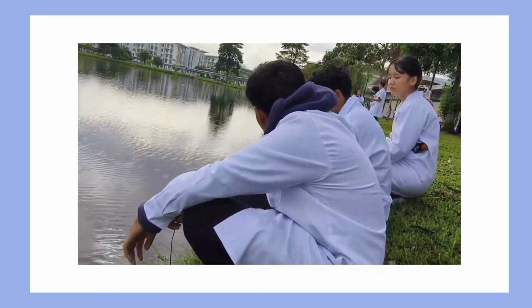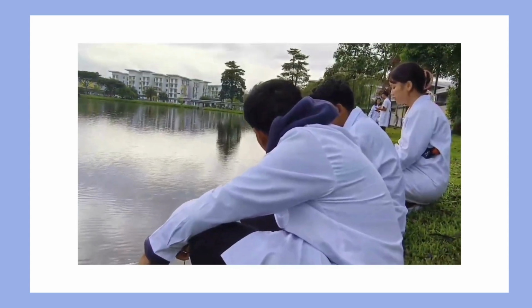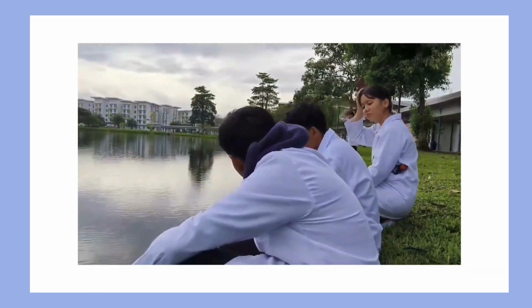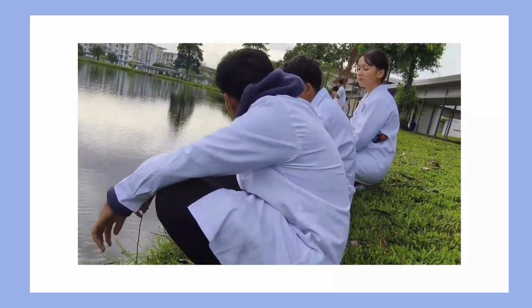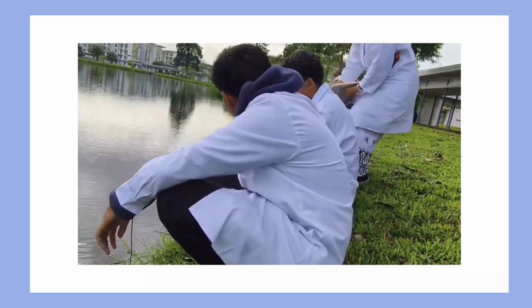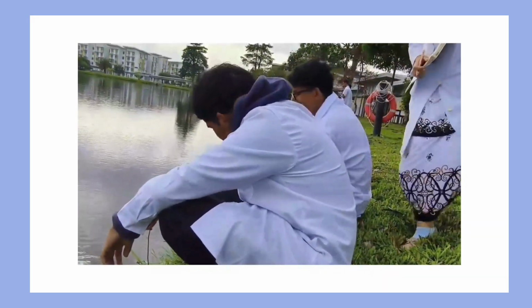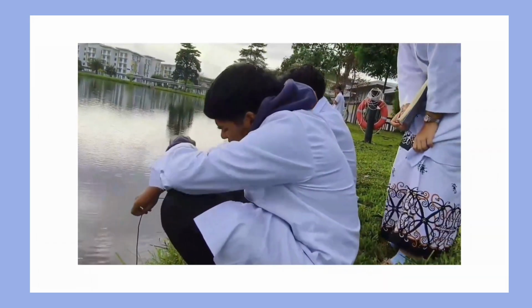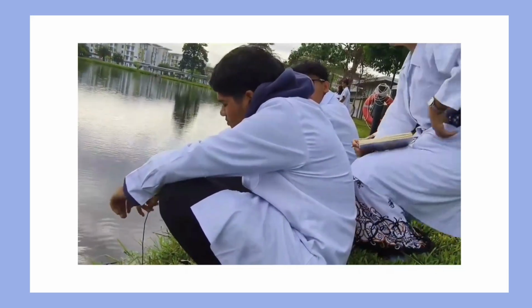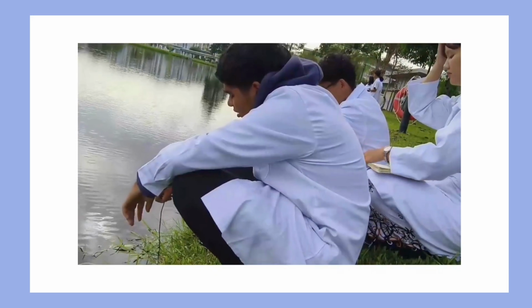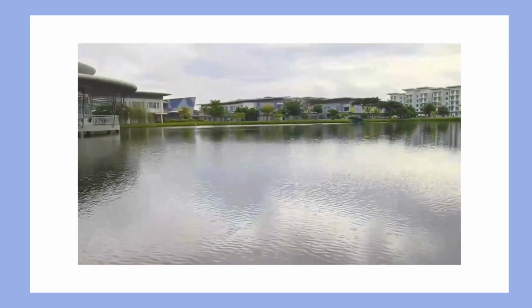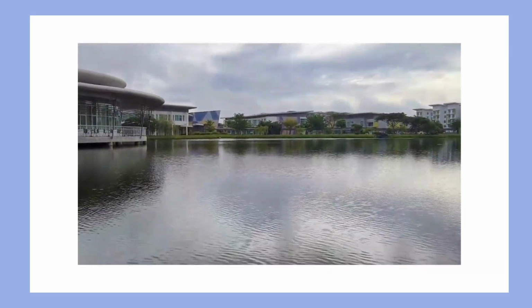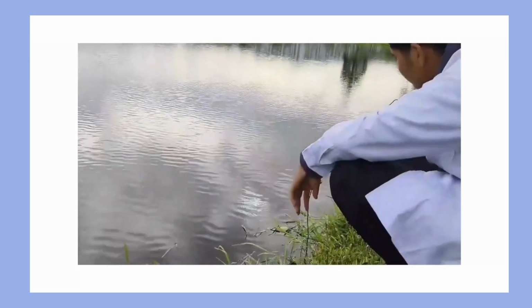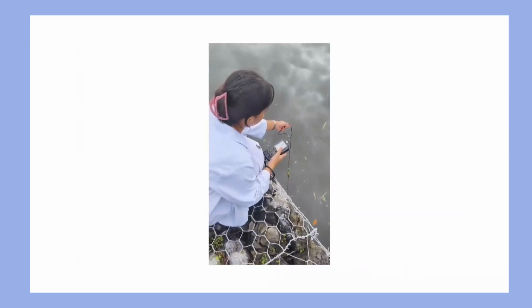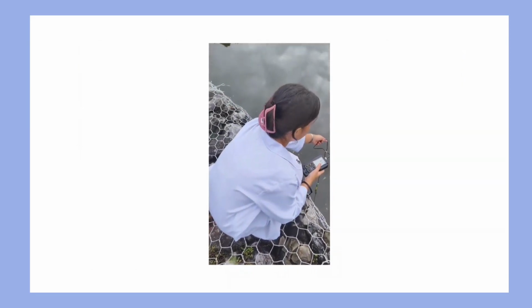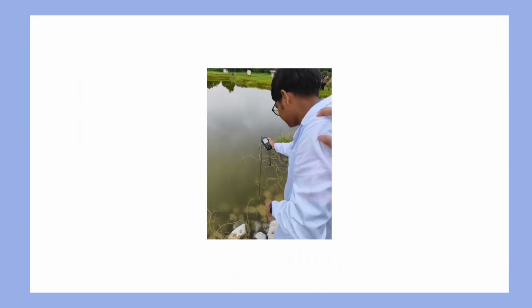Moving on, we are going to measure the pH of the UITM Mocha Lake and UITM Mocha Pond. Firstly, we conducted the measurement at UITM Mocha Lake. After finding a suitable location to conduct this measurement, we started off by recalibrating the device before the measurement started. After the recalibration, we started to dip the device into the lake and suspend it in the middle of the water level. At the first location, we got 7.01 as our pH.